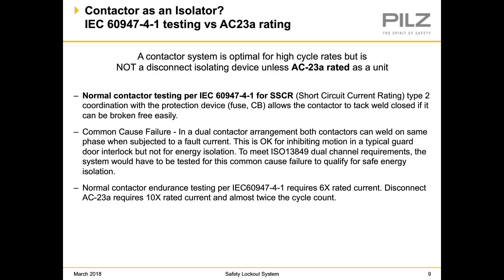So, using a contactor as an isolator. A contactor system is optimal for high cycle rates, but is not a disconnect isolating device unless it's AC23A rated as a unit. Normally, you can see this IEC standard 60947-4-1 that allows a contactor to tack weld closed as long as it can be broken free easily. So if you consider that and you consider a common cause failure in a dual contactor arrangement, both contactors can weld on the same phase when subject to a fault current. This might be okay for inhibiting motion in a typical guard door interlock application, but not for energy isolation.